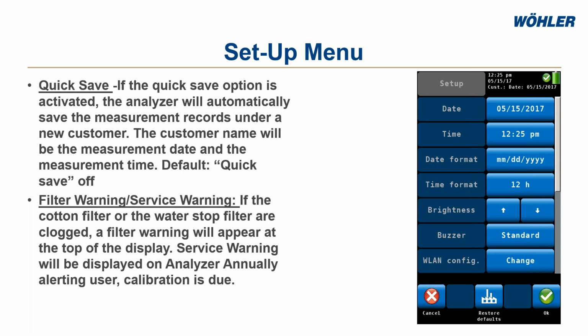Also available is the service warning. If you want your analyzer to alert you when it's time to send in for calibration, you can set that up. It's going to alert you annually. Now, obviously, you can turn that off. Let's say you're 6 months past when it was supposed to be sent in. You can turn that message off if it's annoying.